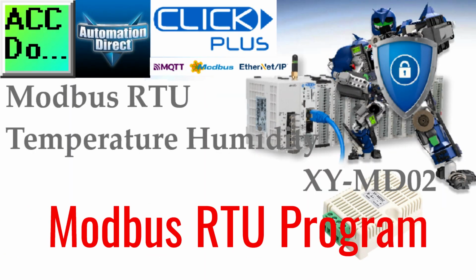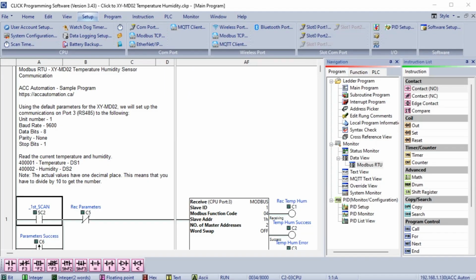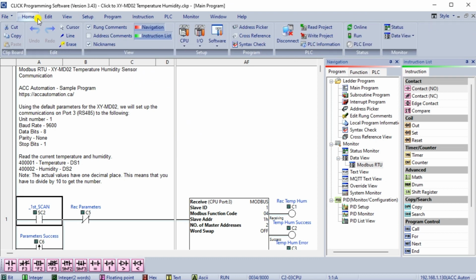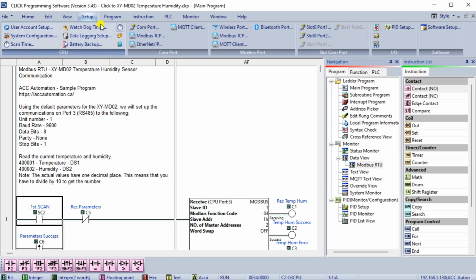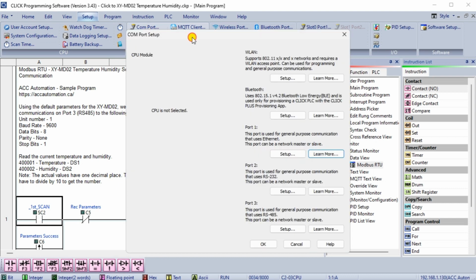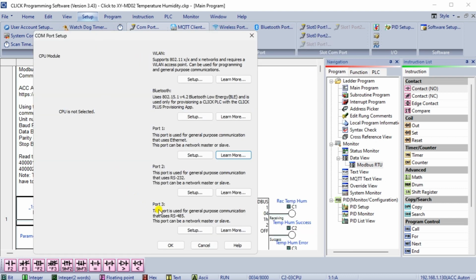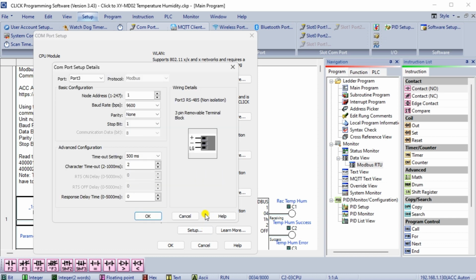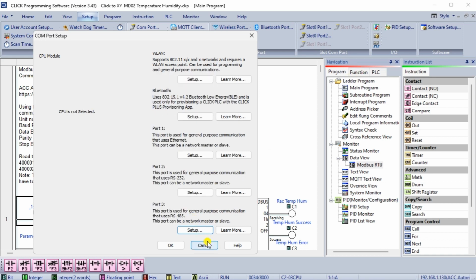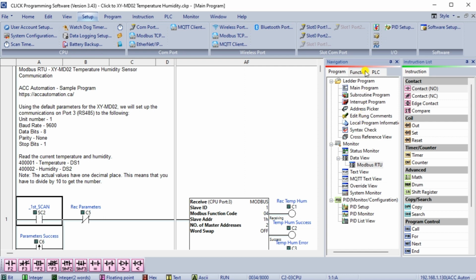Click PLC Modbus RTU program. To communicate to the XY-MD02 temp and humidity sensor, we need to set up the RS485 port on our Click Plus PLC. On the main menu, select Setup COM port. The COM port setup window will now be displayed. Port 3 is the RS485 type that will be used on our network master or client. Select the Setup button. If you want to go directly to the COM port setup details window, select COM port 3 under the CPU configuration on the Function tab of the navigation window.